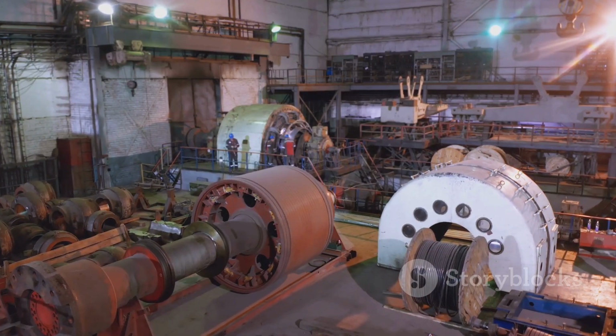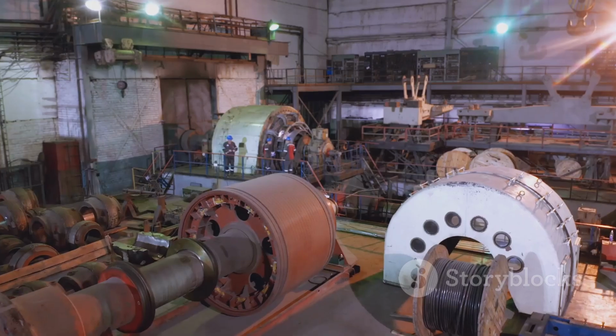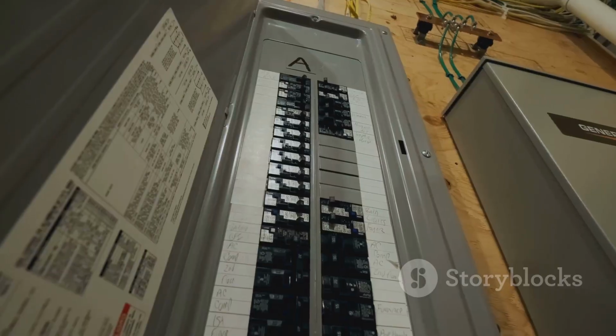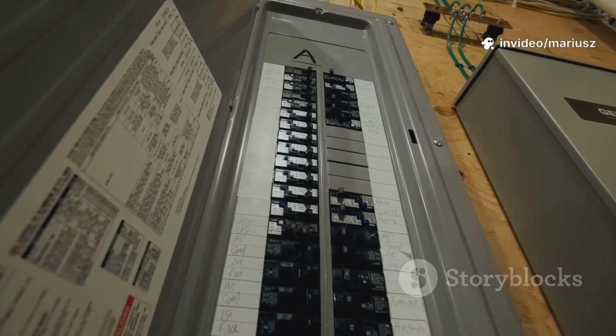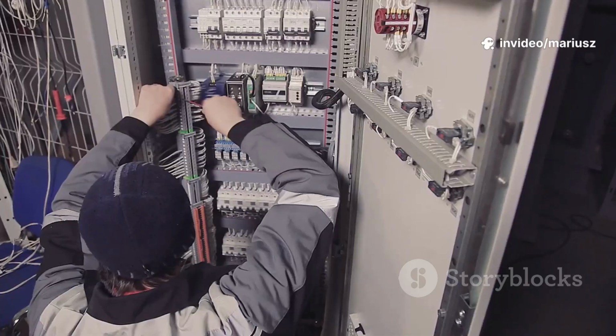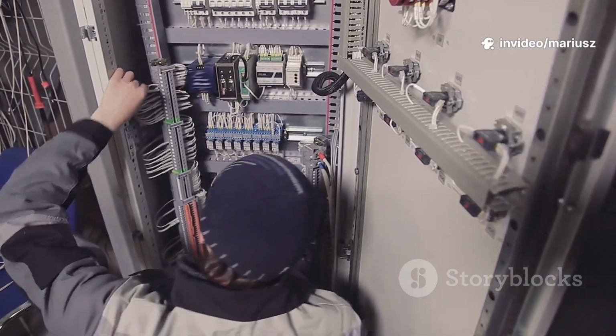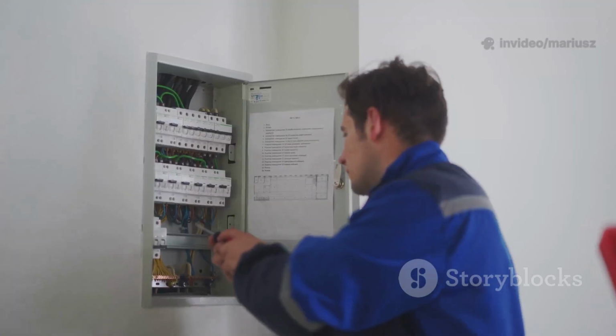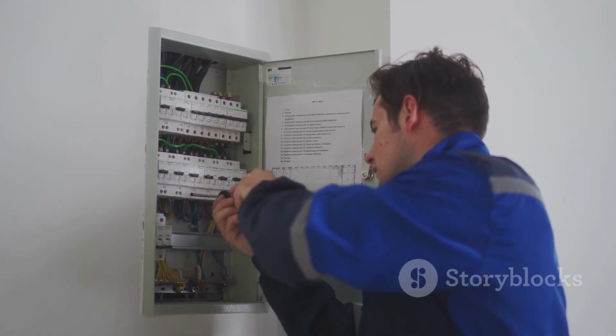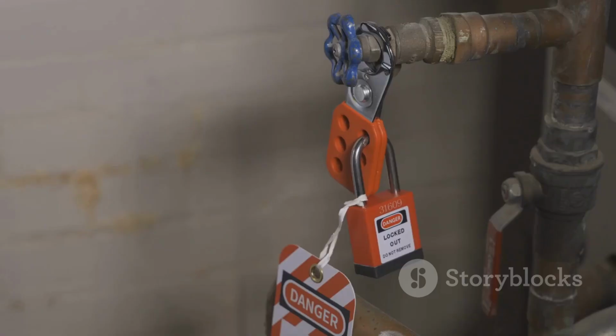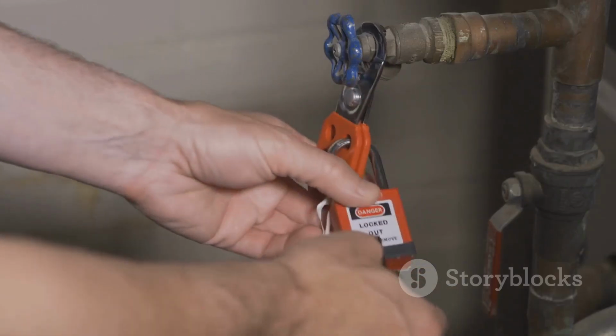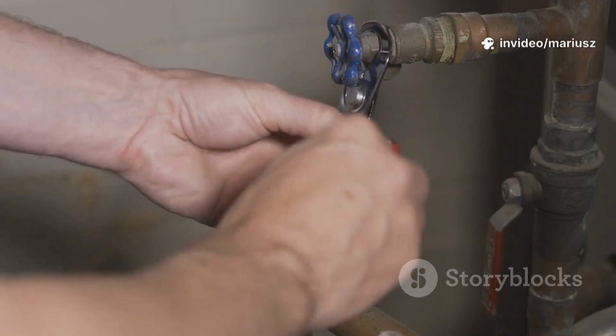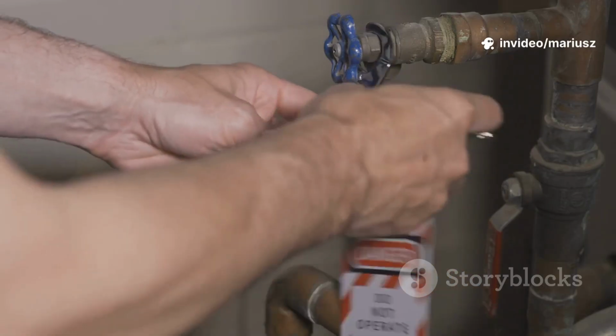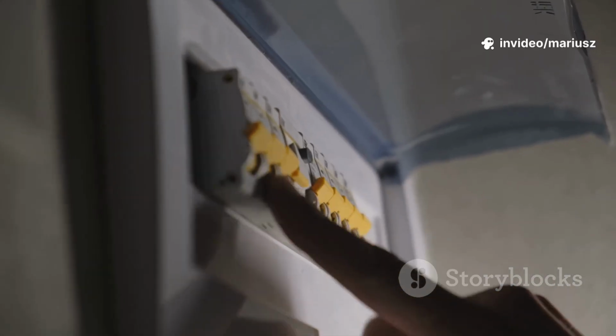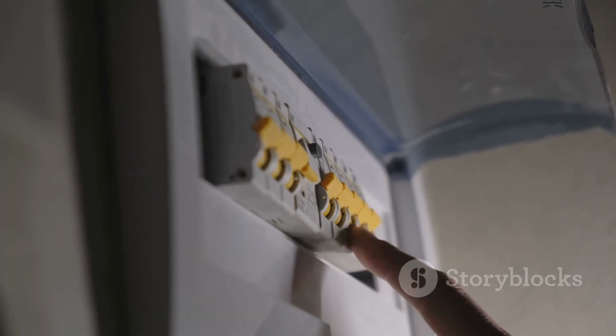Let's use a simple example. Imagine you need to work on a large electric motor. Safety from the system doesn't mean just flipping a switch and putting a sign on it. It means going to the switch gear that feeds the motor and physically racking out the circuit breaker, creating a visible air gap in the circuit. Then, we lock that breaker in the off position with a unique padlock that only an authorized person has the key for. This prevents anyone from accidentally re-energizing the circuit.